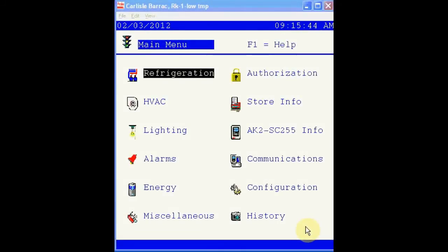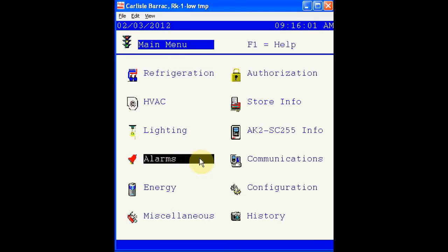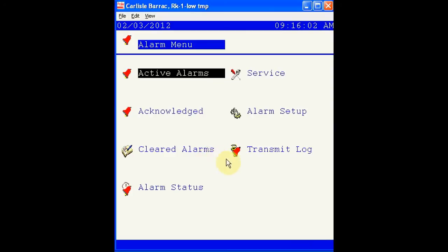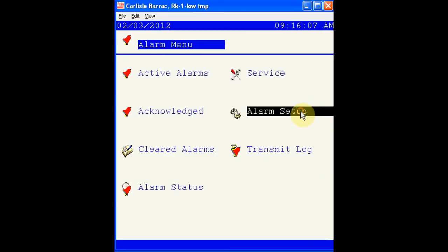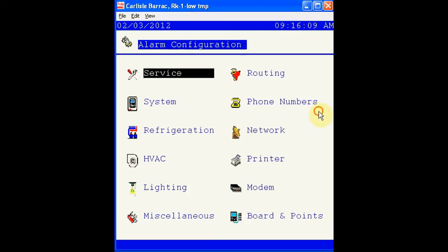Next, let's look into the alarms. Setup of alarms, viewing active, acknowledged, and cleared alarms, and determining whether alarms were in fact sent to other parties so that a correct response can be made. Alarm setup is where most setups are made so that alarms are done correctly.